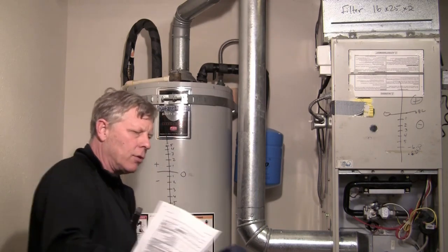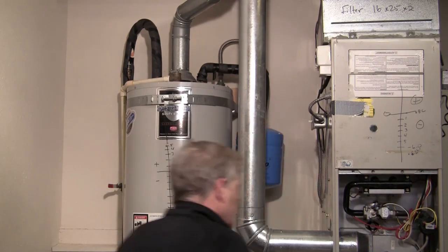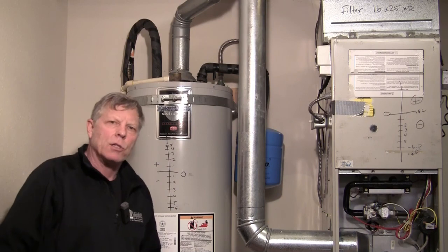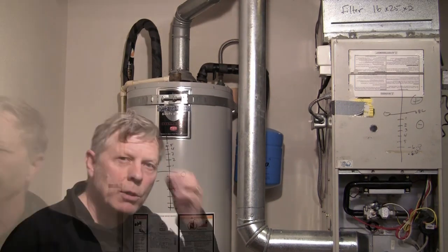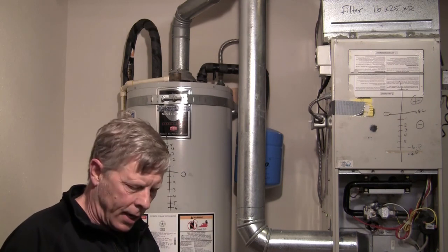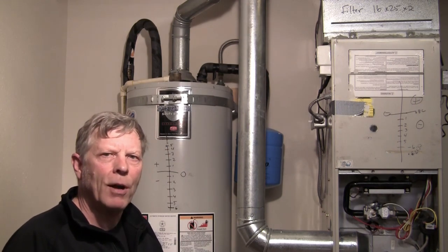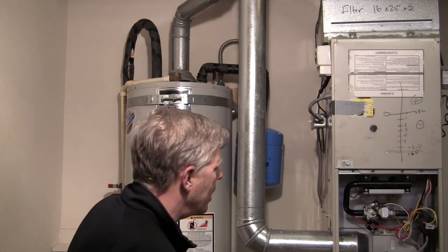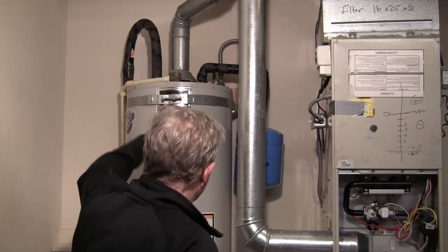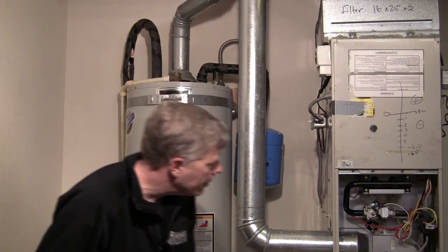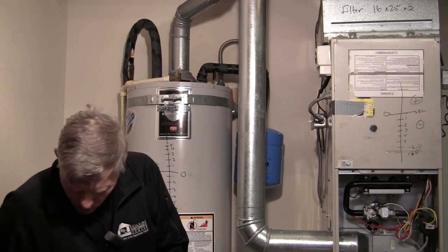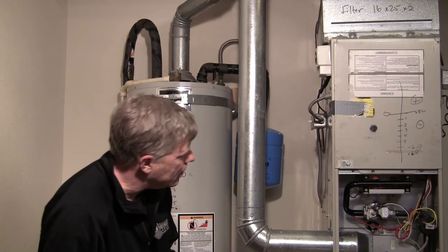Now I'm going to set this back down, and I'm going to go ahead and turn on the furnace. I'm leaving the water heater on. Once the burners start, I'll go ahead and start my 5-minute clock. It has 2 minutes to establish draft. The water heater is still on. It's still spilling. Check my ambient CO while this is starting up. Okay, it's still 0.